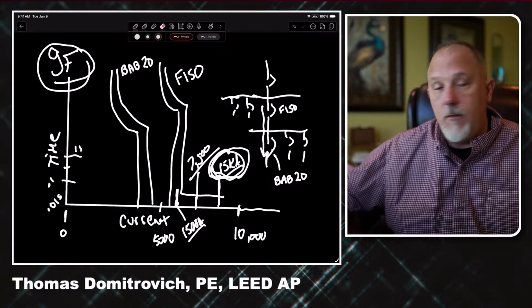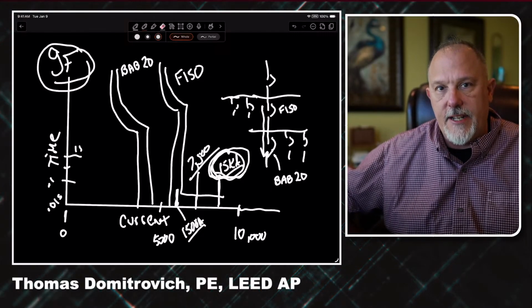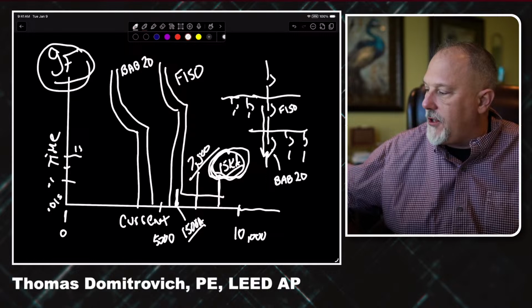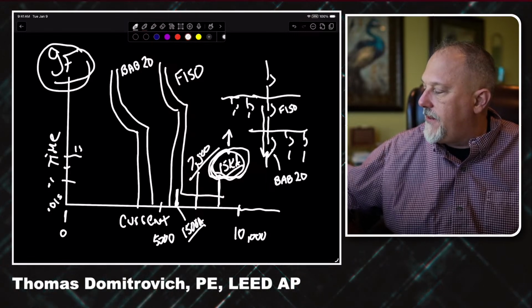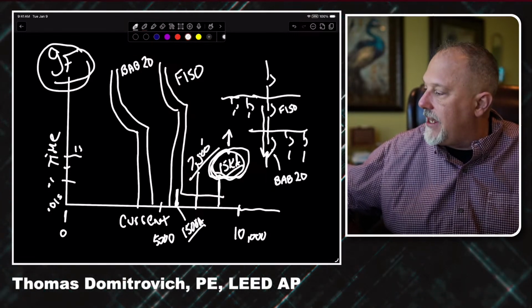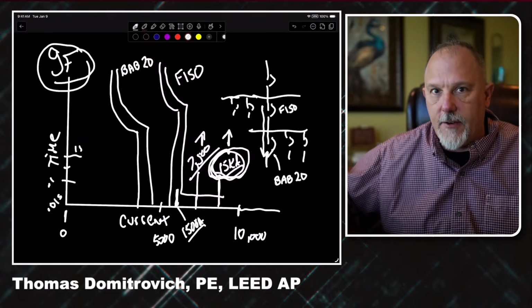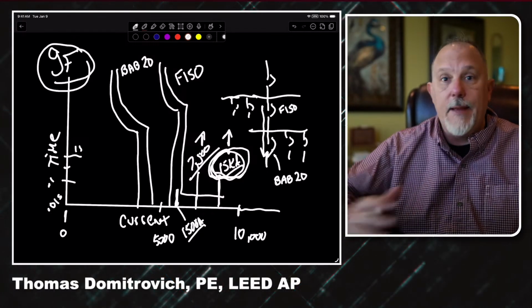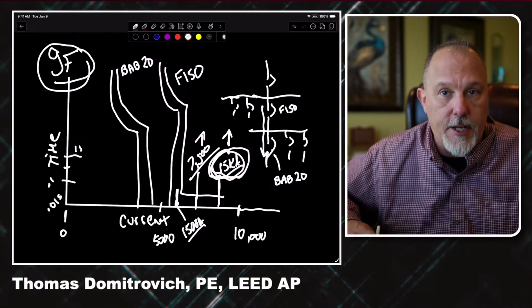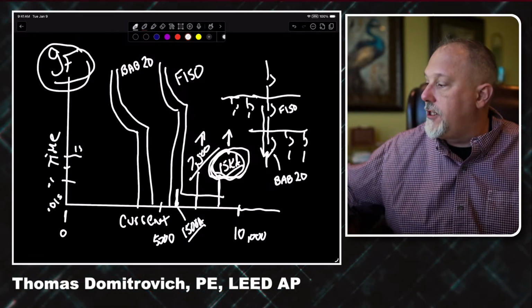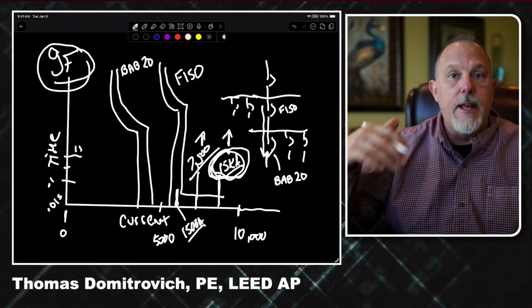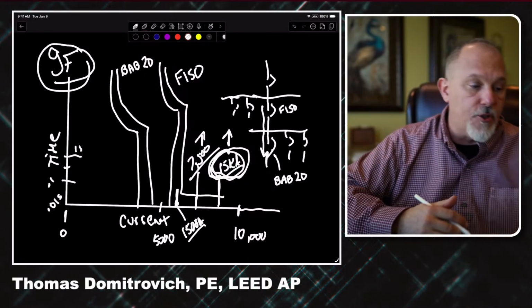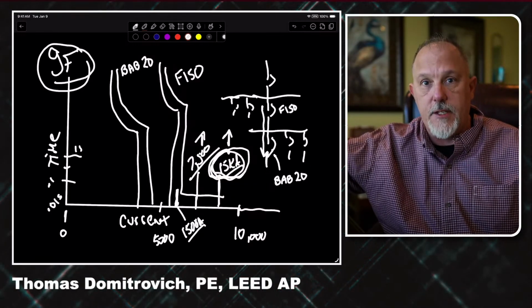So now I know that current makes a difference, and we can argue and debate. Do you selectively coordinate to the 15,000 amps? Do you selectively coordinate to the 7,500 amps? Which one is more common? You might say, well, the arcing current is even more common than that, so you could calculate your arcing currents and coordinate to make sure that the downstream device clears before the upstream device.